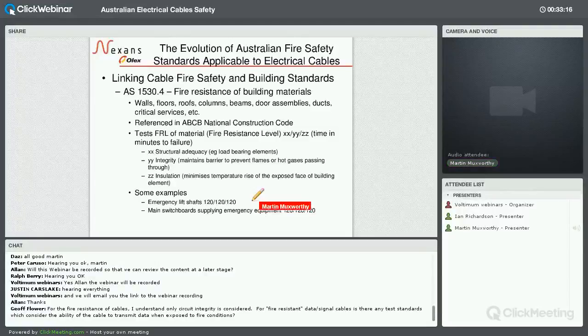Emergency lifts, what I found out in the standard, emergency lifts have a rating of 120, 120, 120, so I mean 2 hours for each of those 3 elements. And I guess it's not surprising that's why cables with a WS52 rating are commonly used for lift mains cabling, for example, and main switchboards supplying emergency equipment, and I guess this relates to things like your fire pumps and emergency lighting and so on, which also have the 2-hour fire limit. That's essentially the end of my presentation.